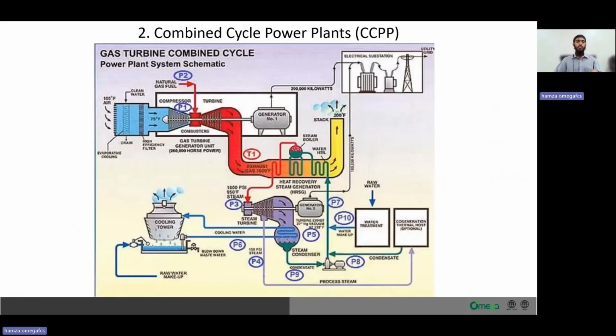Moving on to the next one, here we have the combined cycle power plant. A combined cycle power plant integrates gas and steam turbines to generate electricity with high efficiency. The main components are a gas turbine, a heat recovery steam generator, and then a steam turbine. These work together, with the gas turbine exhaust heating water in the heat recovery steam generator to produce steam, which then powers the steam turbine.